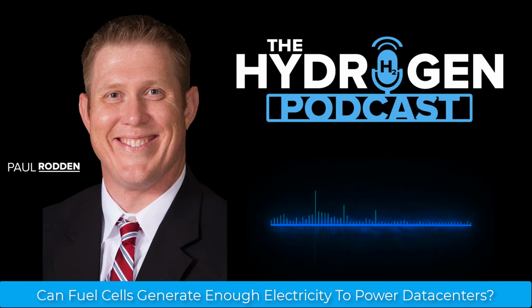A 3 megawatt system is of sufficient size to replace a diesel generator at a data center. The problem, Monroe noted, was that nobody made PEM fuel cell systems that large. 3 megawatts is more than 10 times bigger than the system the company tested in Utah, and is enough energy to power about 10,000 computer servers or 600 homes.